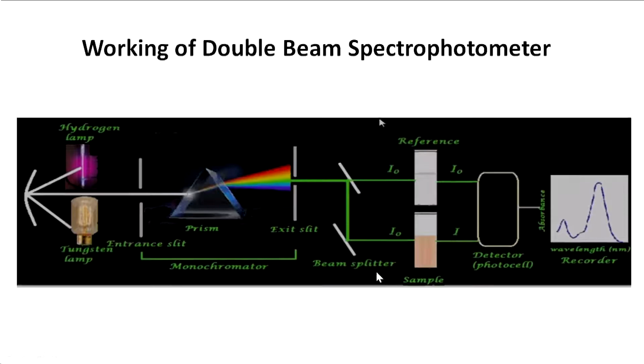This is the overall working of the double beam spectrophotometer. Here, the difference from a single beam spectrometer is that the light coming through this prism is split into two equal halves by a beam splitter, and then they are allowed to fall simultaneously on the reference cell and on the sample cell.